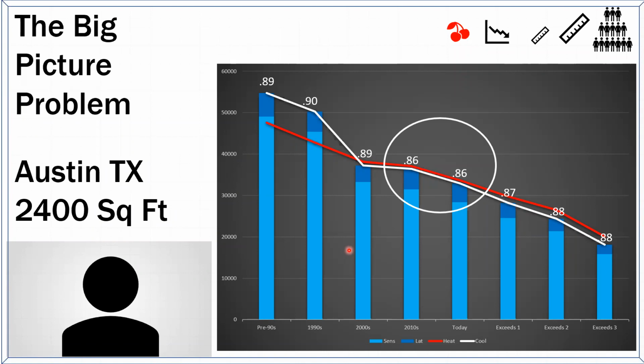Looking at this load calculation, the sensible heat factor is 0.89 and 0.9, so I'll just round that to 0.9 for the older homes. That means, on a design day, 10% of the energy was needed to control moisture. And in the early 2000s, still about 10% of the energy was needed.